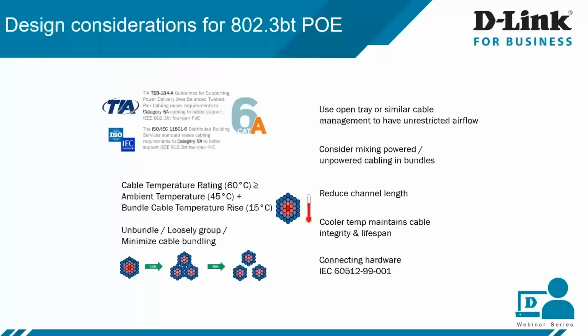Limit the bundle sizes to ensure the temperature rise is not more than 15 degrees centigrade, giving a gap between your operating temperature and the rise in temperature plus ambient temperature. Cooler temperature maintains cable integrity and lifespan.